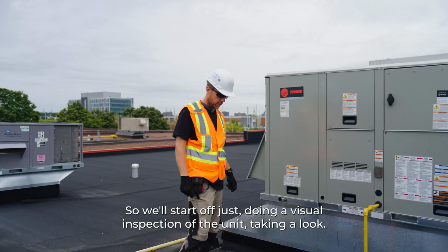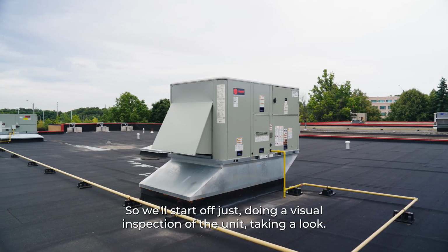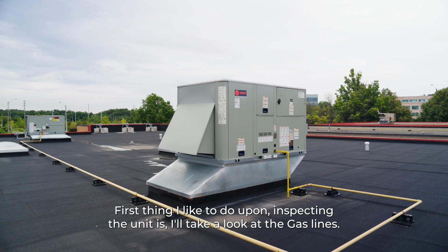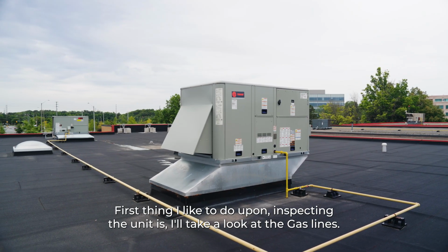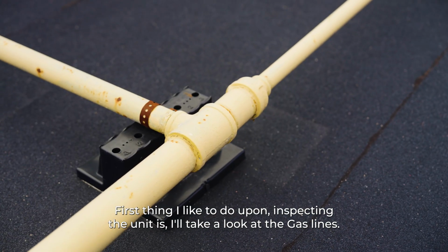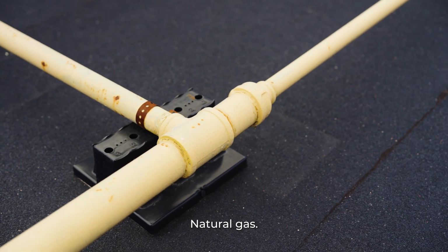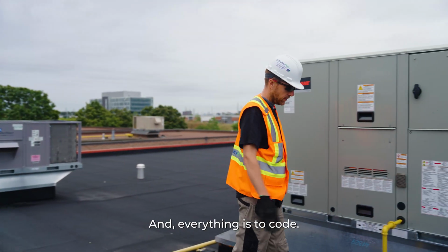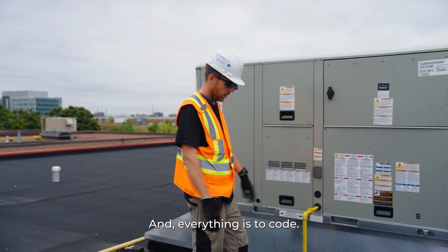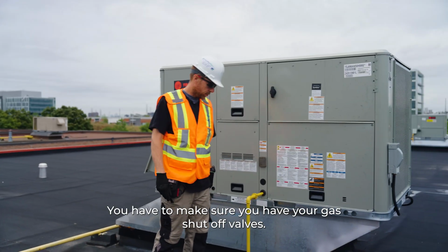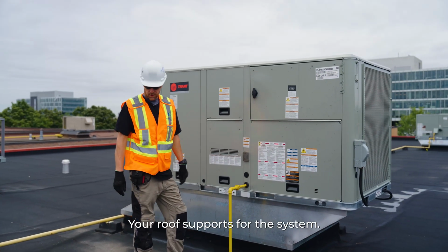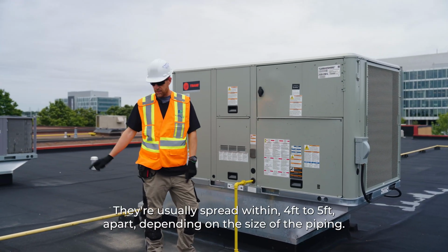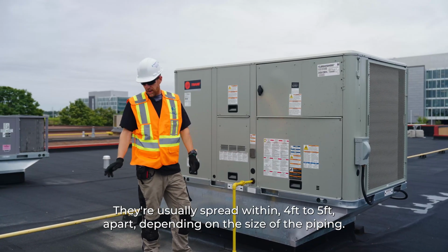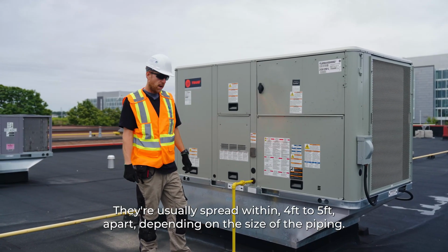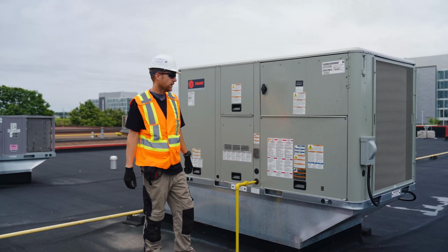So we'll start off just doing a visual inspection of the unit, taking a look. First thing I like to do upon inspecting the unit is take a look at the gas lines, natural gas, making sure that everything is painted and everything is to code. You have to make sure you have your gas shutoff valves, your roof supports for the system. They're usually spread within 4 feet to 5 feet apart, depending on the size of the piping.